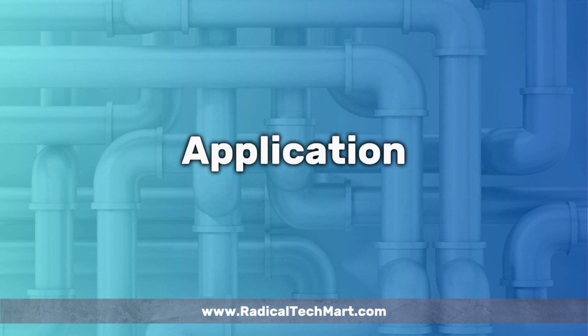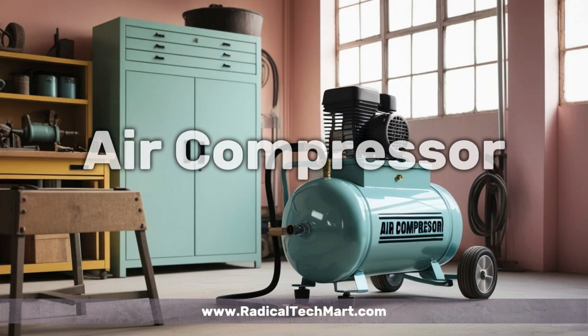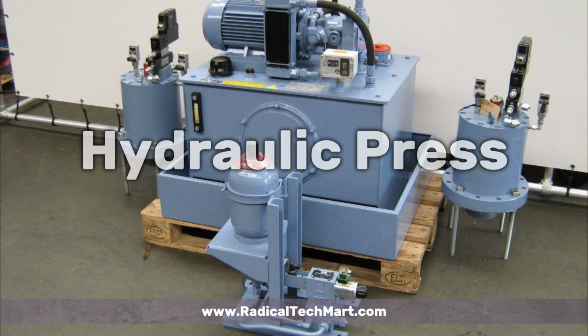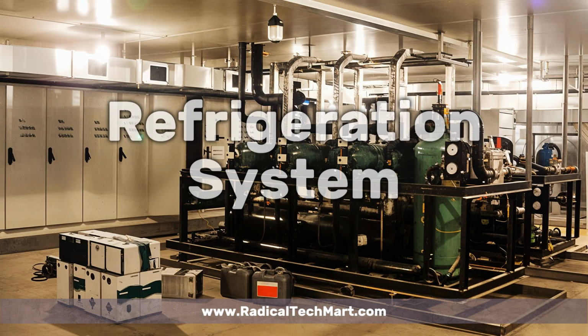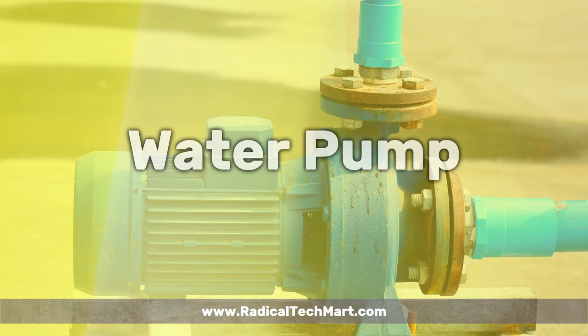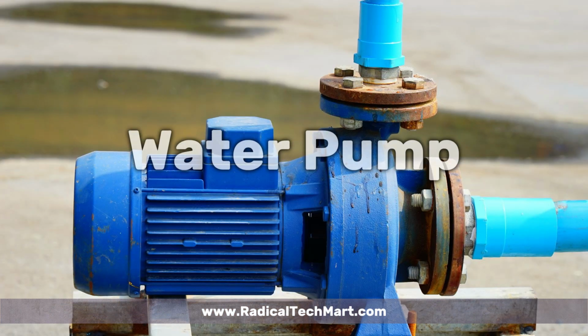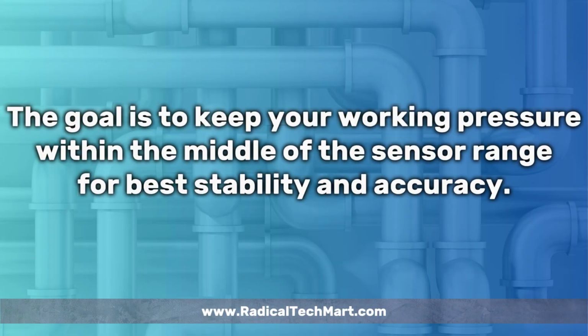Let's see a few examples. Air compressor, working pressure 8 bar, use 0 to 10 bar range. Hydraulic press, operating at 160 bar, use 0 to 200 bar. Refrigeration system, vacuum to 10 bar, use -1 to +9 bar. Water pump, pressure 6 bar, use 0 to 10 bar for safety. The goal is to keep your working pressure within the middle of the sensor range for best stability and accuracy.